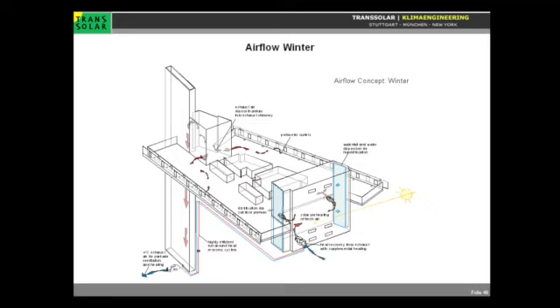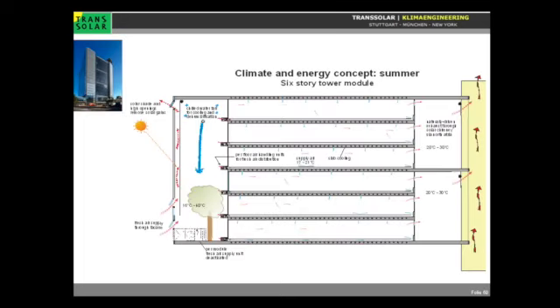So the supply comes all through the raised floor locally, but the exhaust is just collected, because we are not mixing the ventilation air in the space. We get a very stable stratification, so we can collect the exhaust air even in a 3 meter high space, and shift it or collect it over a length of around 100 feet to the exhaust shaft.